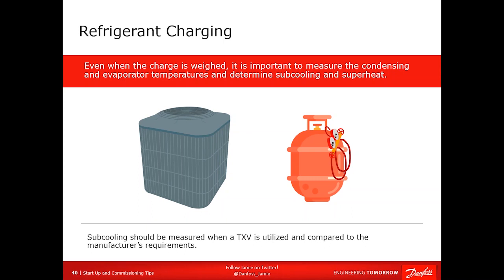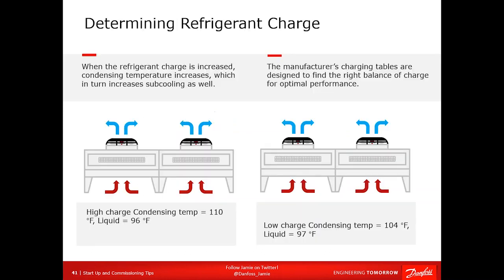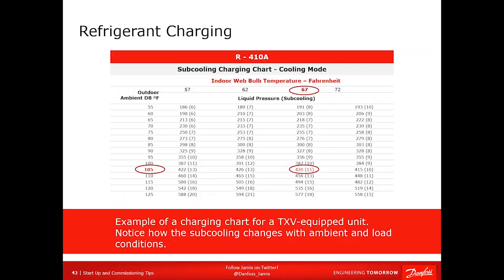All right. Even if you weigh a charge in, always check superheat and subcooling to make sure everything else is working properly, because airflow, you name it, also affects these values. And you don't know, there could be extra piping, there could be extra parts, there could be an oversized dryer, who knows what. That could affect the charge. So for a TXV system, when you charge, you are increasing your condensing temperature. When you increase your condensing temperature, you're increasing your subcooling, regardless of what causes it. So when you're charging a system with a TXV, you charge the subcooling.